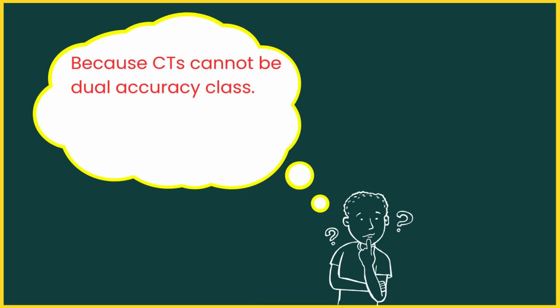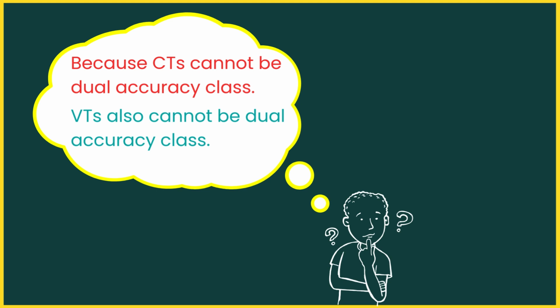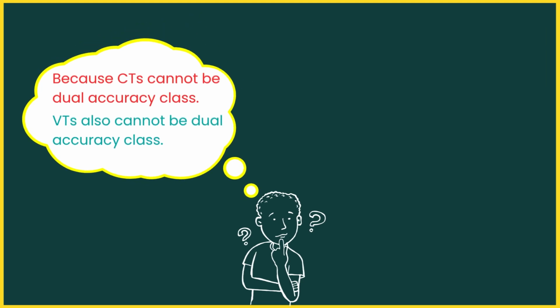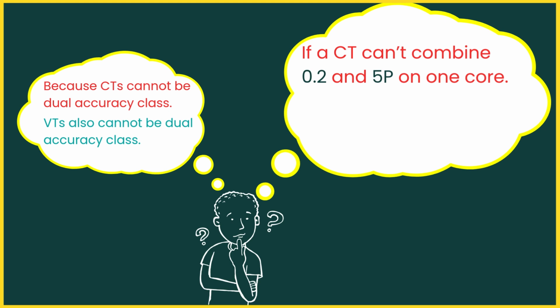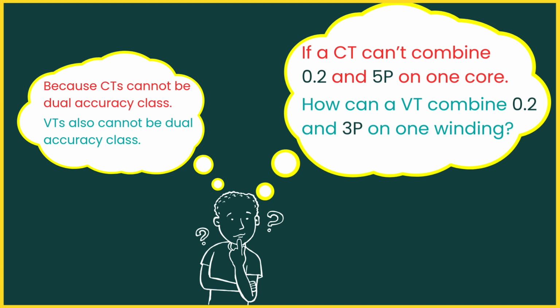Many engineers believe that because current transformers cannot be dual accuracy class, voltage transformers also cannot be dual accuracy class. After all, if a CT cannot combine 0.2 and 5P accuracy class on one core, then how can a VT combine 0.2 and 3P on one winding? It sounds logical, right? But it's not true.